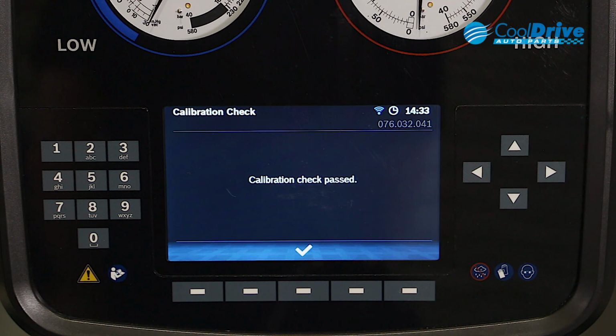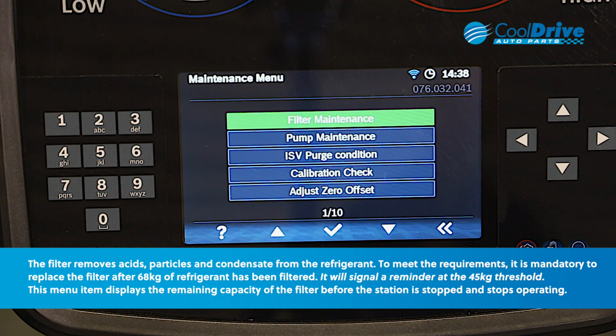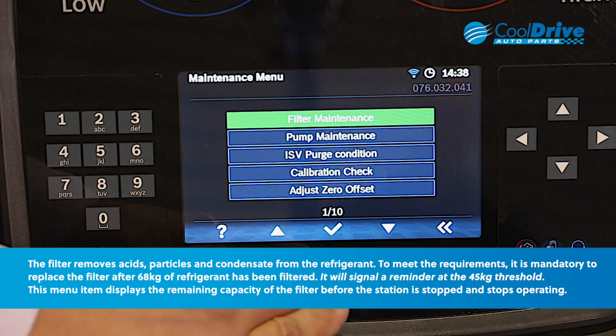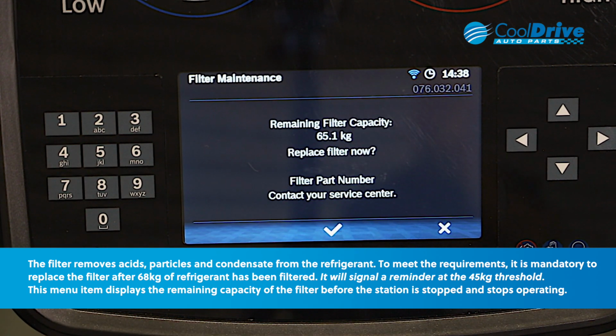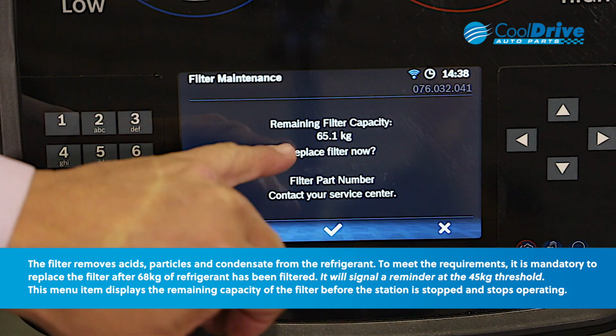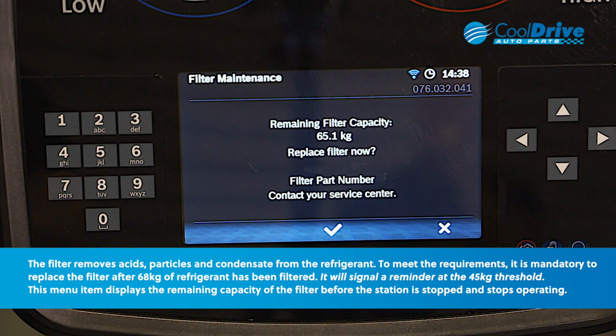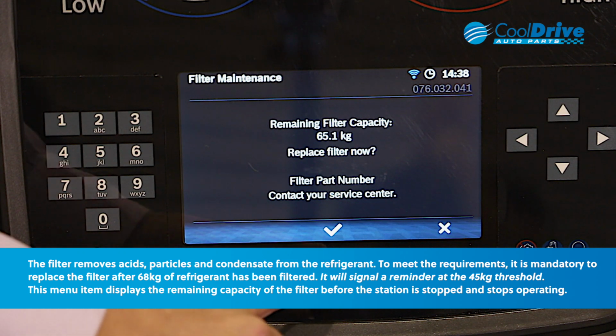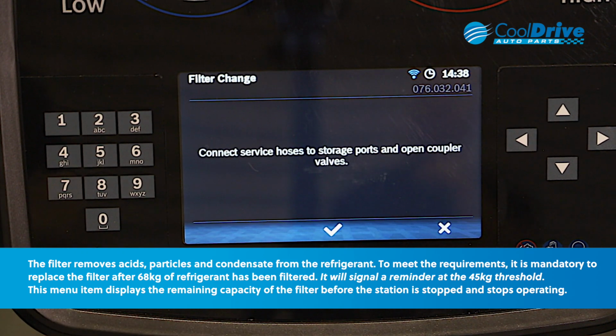If there is a calibration issue, it will fail the calibration test. At 68 kilos of refrigerant usage, the machine requires a filter change. It gives you a warning at the 45 kilogram mark that this needs to be performed. You need to access the filter maintenance program from the maintenance menu. We press enter, it prompts us of how much refrigerant capacity we've used and whether we want to replace the filter now. If we decide to change the filter, we click on enter.